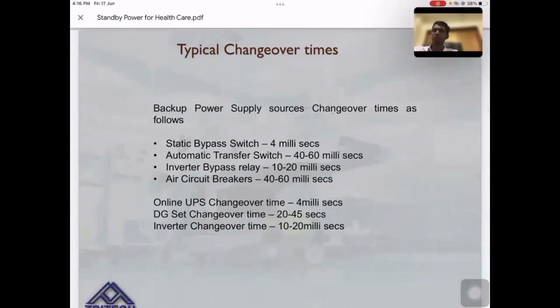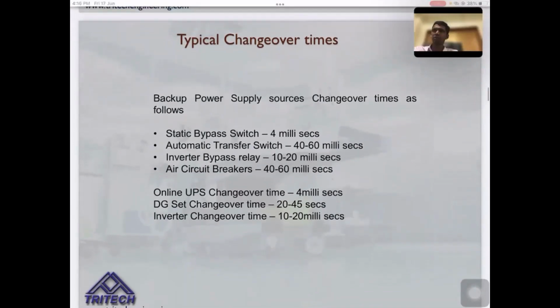If you look at the changeover times of various equipment, you can see that there are static bypass switches, which are thyristor drive based bypass switches, which are the fastest, closing in around 4 milliseconds. Then we have the automatic transfer switches for transferring power between the generators and utility and vice versa, which is actually a mechanical equipment that takes around 40 to 60 milliseconds. Similarly, there are inverter bypass relays, which again have a shorter time, 10 to 20 milliseconds. You may not notice them. And we have, of course, the air circuit breakers, which may take somewhere between 40 to 60 milliseconds.